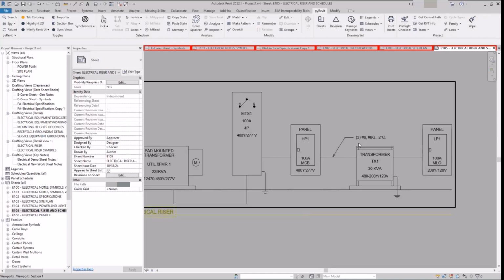That way, if anybody ever goes, how did you get this size? Great, I go pull up that PDF, and normally I'll put NEC references in there, especially if it's something I'm not incredibly familiar with. This code says this, that one says that, so I followed the other one because it was a stringent requirement, and I sized it like that, showed my basic math, and ta-da, I get a number 8 right here, which, as a reminder, I literally threw in here last video. I don't know if it's actually sized properly. So that's the engineer's hat.